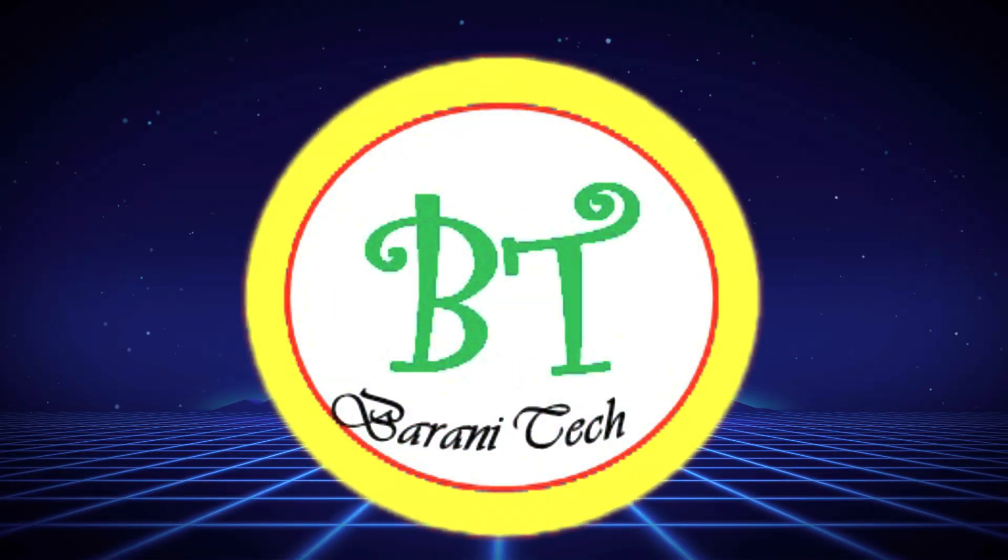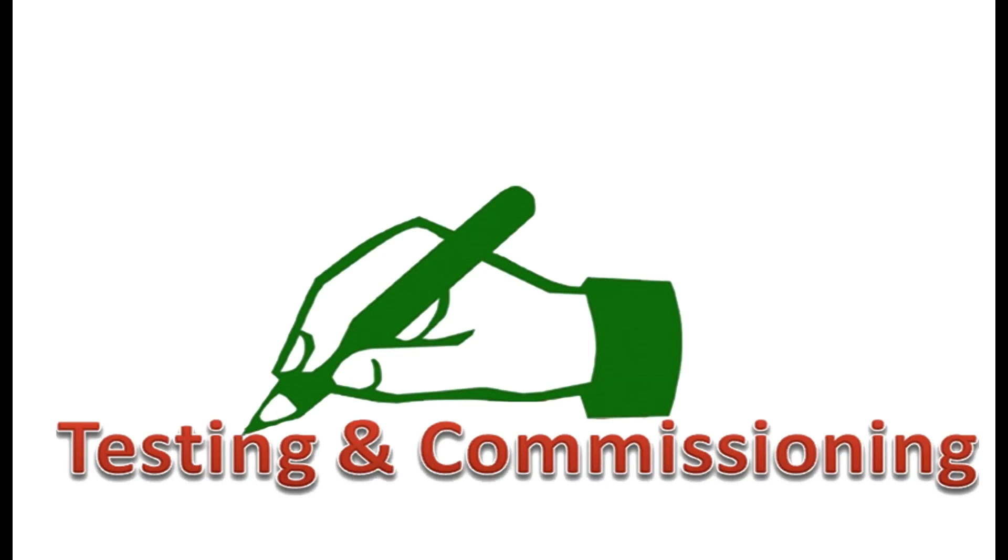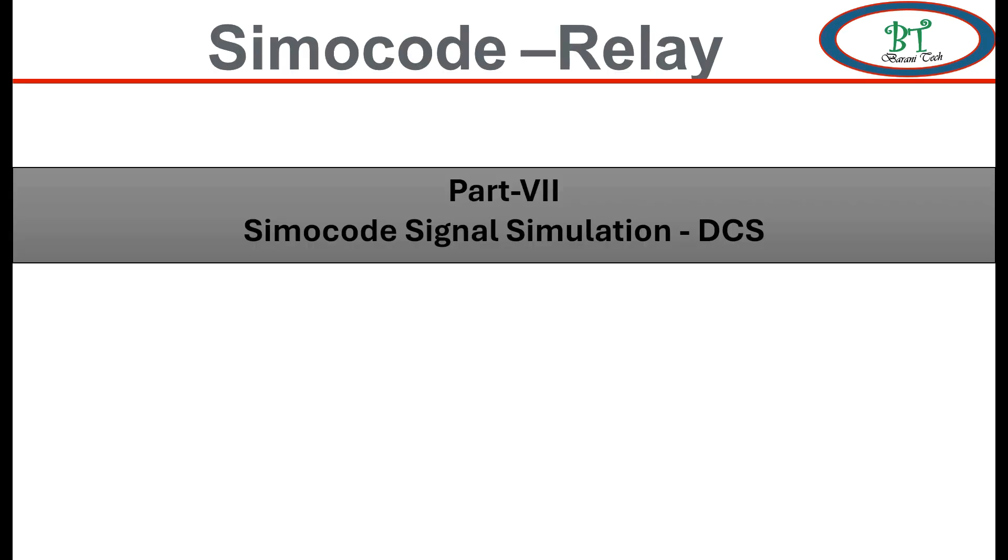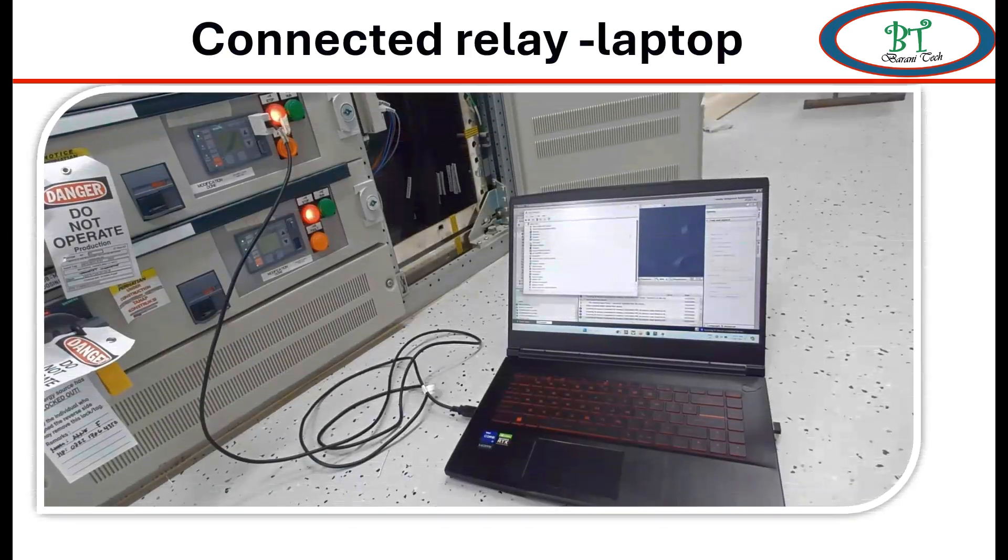Hi, welcome to Barani Tech channel. In this section, I am going to show the relay to DCS signal simulation on Simocode relay through TIA portal software. First, we should know this kind of simulation testing signal from relay to remote end can be done only on test position.